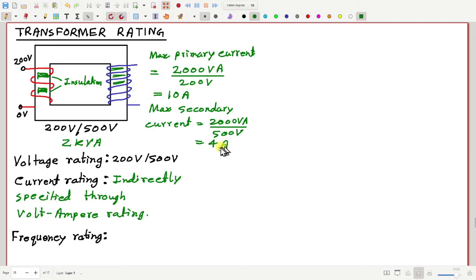So if we operate this transformer beyond these specified levels of currents, the transformer may get damaged, it may cause severe accidents. Now, the third important rating about a transformer is the frequency rating. So for example, I can say that this is a 200 volt by 500 volt 2 kVA 50 hertz transformer. What does this mean? It means this transformer is supposed to work under 50 hertz frequency, and normally we can increase the frequency, but we should not decrease the frequency.